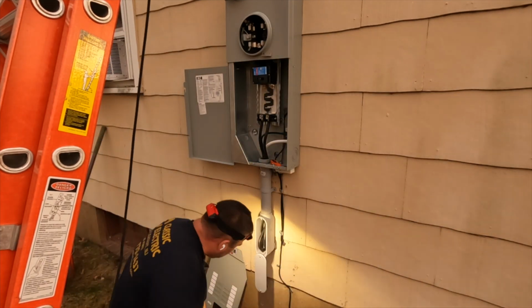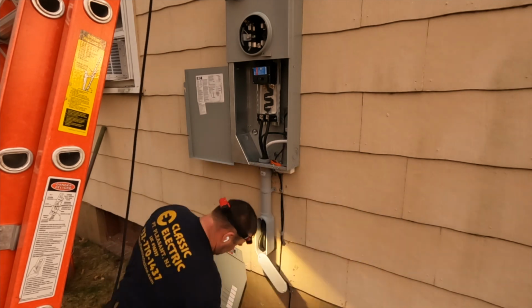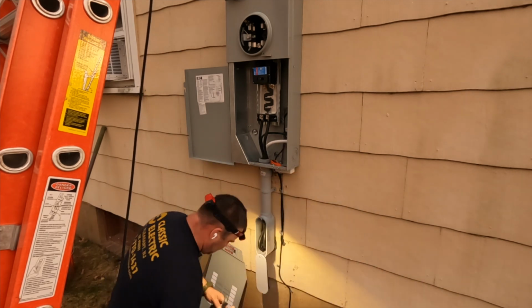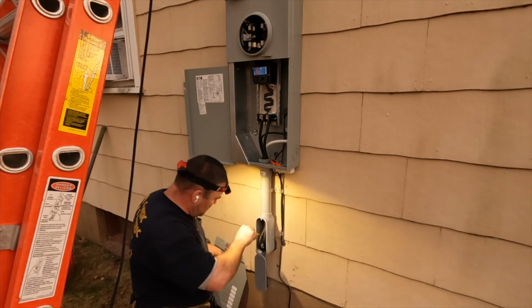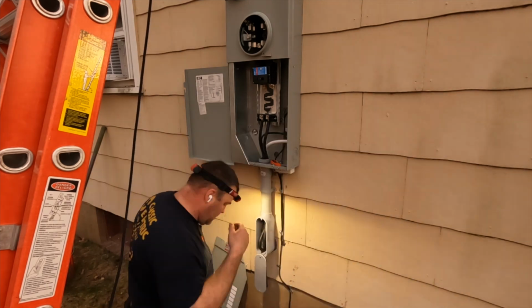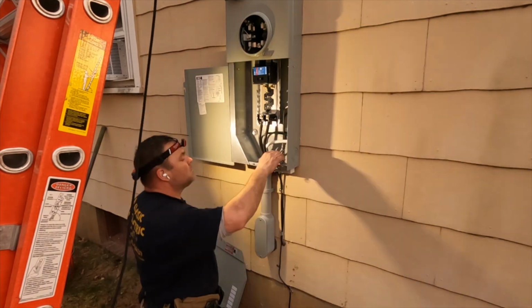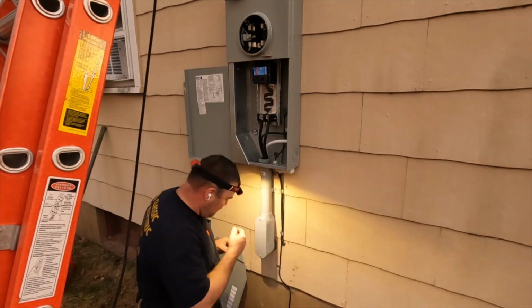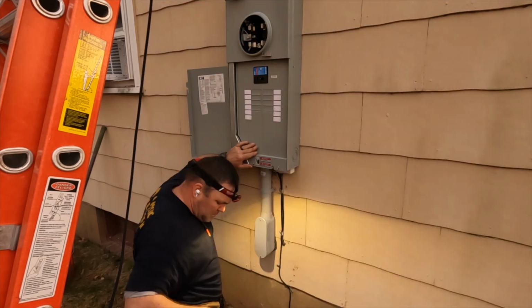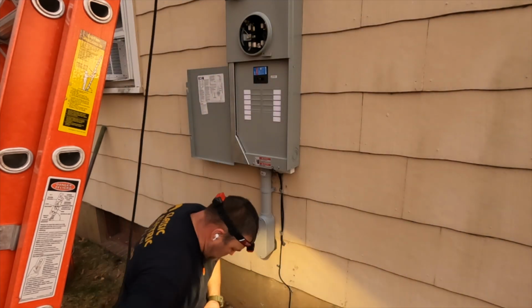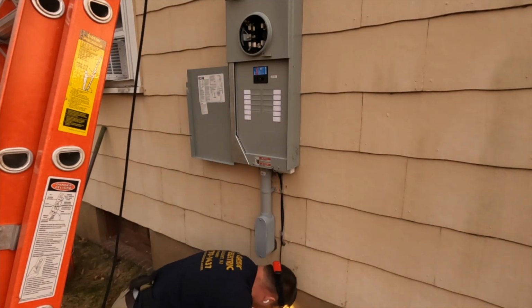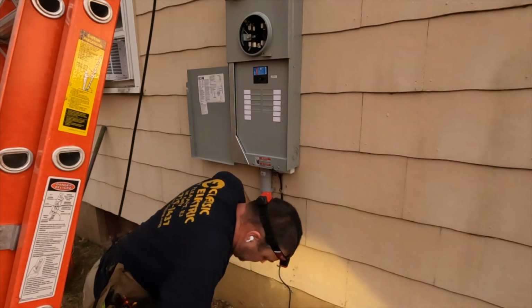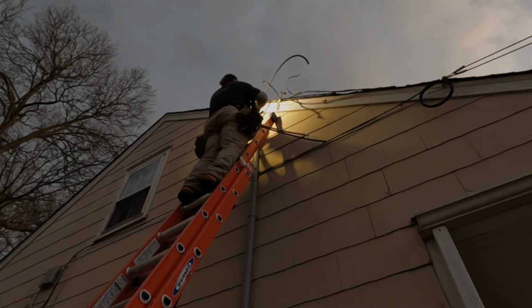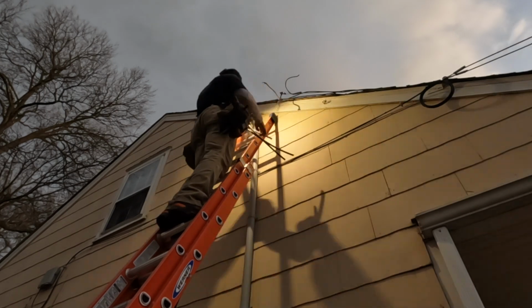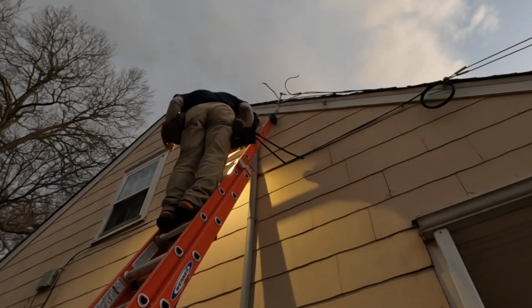So here I'm putting in the duct seal between the outside and the inside. That's the leading cause for rust and condensation inside an electrical panel, is that cold air meeting the warm air on the inside, forming condensation, and it just goes inside your panel and just wreaks havoc. So the code actually requires that we plug up that raceway between the outside and the inside, just to prevent the condensation from forming. All right, so we are coming to the end of the video here.